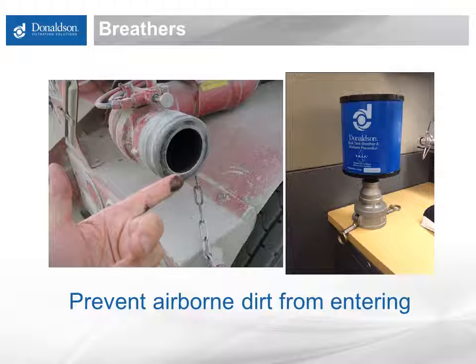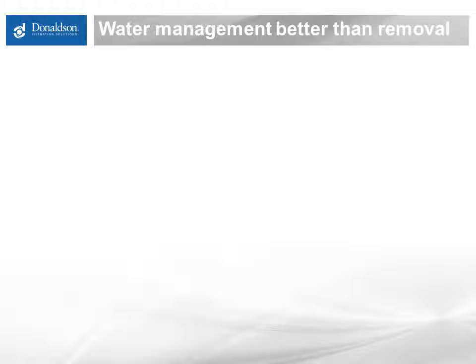It needs to be appropriately sized to not build up too much pressure or vacuum as air is going into the tank, but that is a way to keep particulate from ingressing into that tank, and then when you fill it with the next load of fuel, it gets filled with the dirt that settled out from the air coming into the tank. So that's another very proactive way to keep the dust out of the area. If you're working in a job site where you can actually sort of taste the dirt, you know that is also getting into your fuel, it's going into your breathers, any open pipes on tanks, that kind of thing. And you need to prevent it.